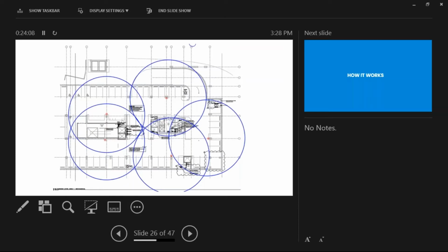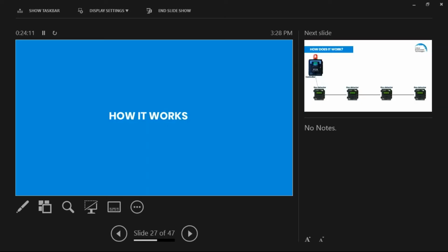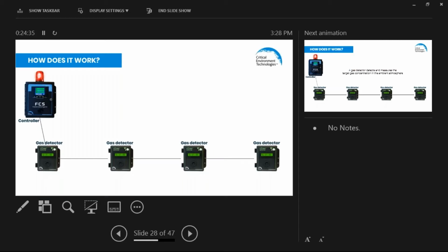And just a couple more examples there. And so now you've got this little sensor element, and you've got a number of sensor transmitters, or maybe even a standalone self-contained system within that building envelope. But how does that actually work? How does that interface to the ventilation system and ventilate out any buildup of toxic gas? Here's a little example of a system approach wherein you have a centralized controller and a number of gas detection sensor transmitters placed throughout that building envelope.